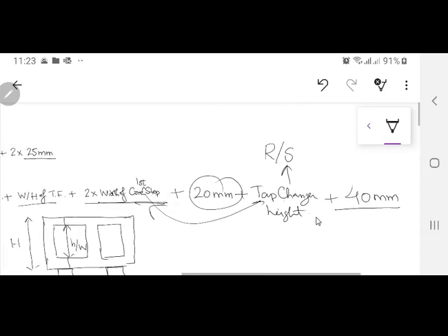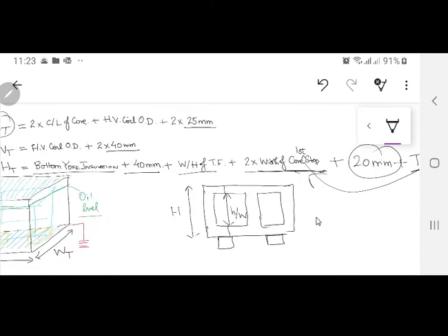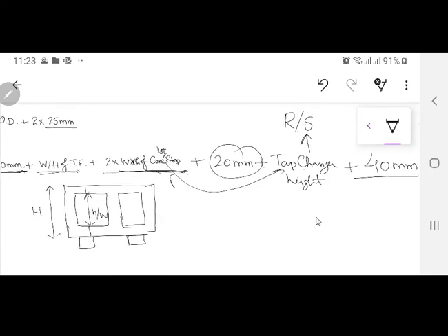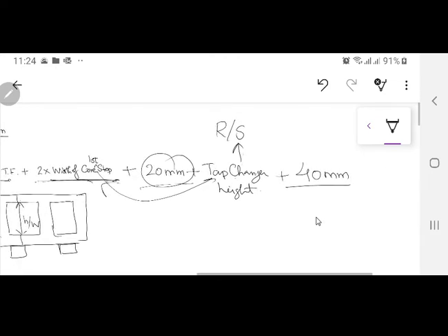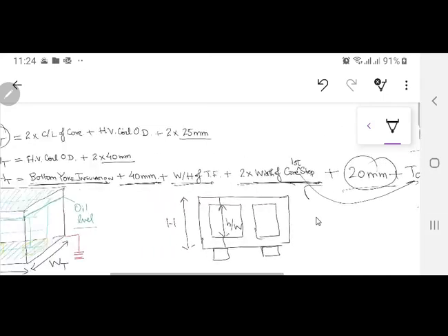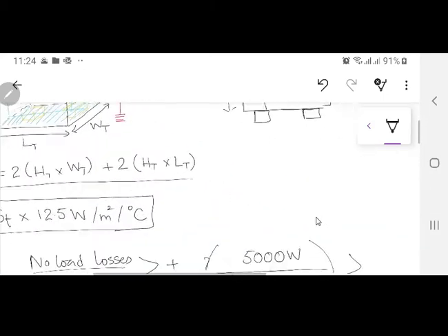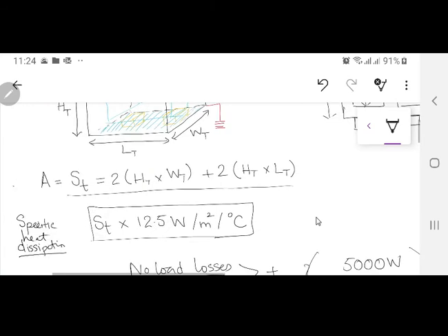So the height is a little complex over here. As you can see, height is equal to: bottom yoke insulation, 40 mm added just to have a clearance distance so that oil can be there, plus window height of the transformer, plus the width of the first core step, plus 20 mm the gap between ratio switch and transformer, plus the ratio switch height, plus 40 mm the clearance distance. So this is the height of the transformer tank, and now you have all 3 values. You can then find out what is your A area or St area.